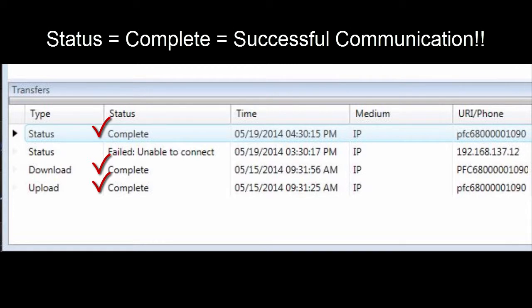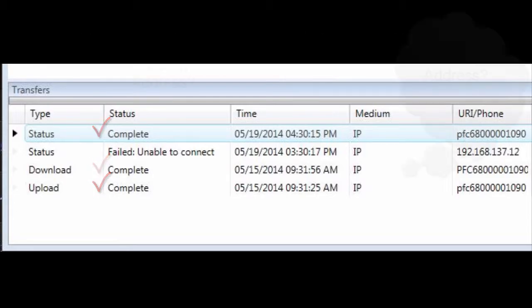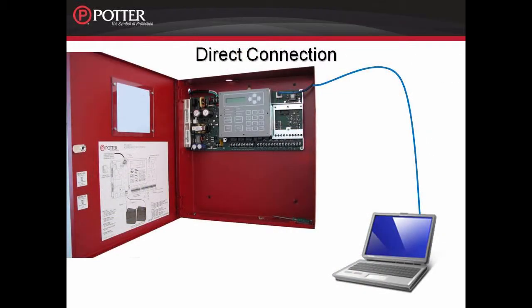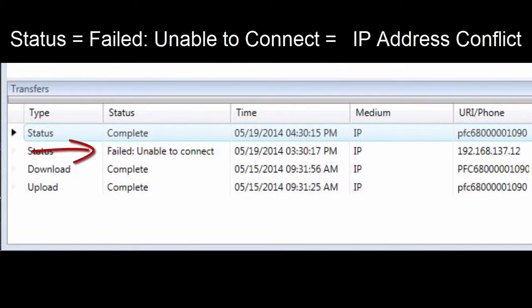In order to have successful communication between the fire alarm control panel and the computer when direct connected, the IP address on the panel and the computer need to be similar. For example, if the IP address of the panel is 169.254.150.70, then the computer needs a similar IP address but not the same — for example, 169.254.150.75. When communicating with the fire alarm control panel from a laptop computer with a direct connect, the common error you'll see when the IP addresses are not similar is "Failed - Unable to Connect," seen in the transfers window under status.